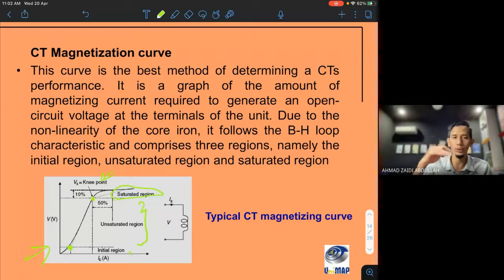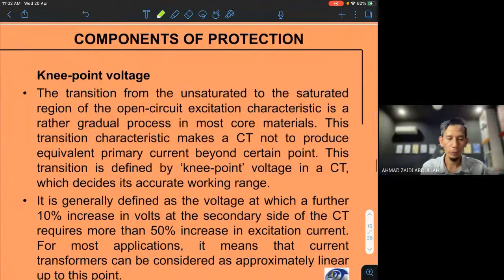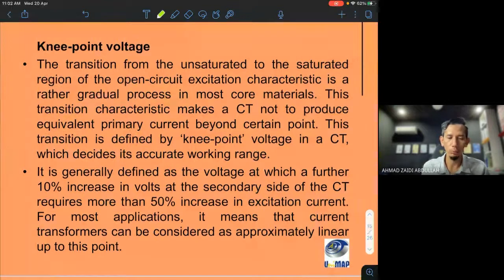It is already saturated, that region. So normally we don't use that area; we try to avoid it. And this is the only working area for the current transformer. Okay, what is the knee point? The knee point is the transition from the unsaturated to the saturated region, the last point. Already saturated, the output stops from there.